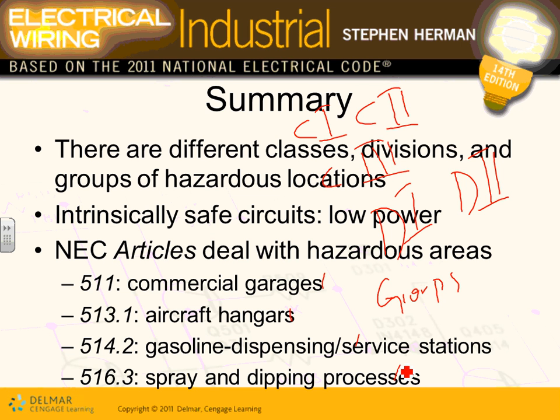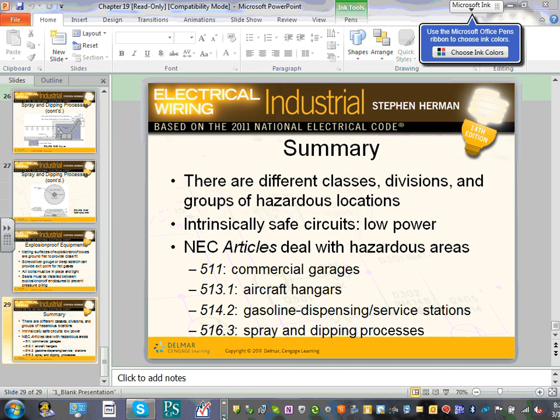Don't forget that for your instrumentation, you have a really nice circuit called an intrinsically safe circuit, so you don't have to worry about explosion-proof. But that's for instrumentation. Can an intrinsically safe circuit, guys, feed a fixture like this? No. That's just for getting a sensor, sensing the pressure and the temperature and what's going on. And that's a big deal. When you have a chemical process, don't you think you want to know what's going on in that process without exploding it? So I have a couple of pictures I'm just going to go over, and then that's it.